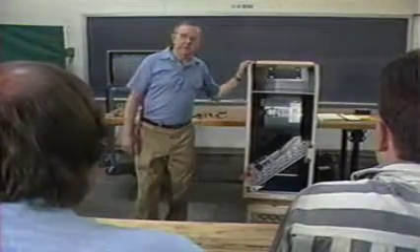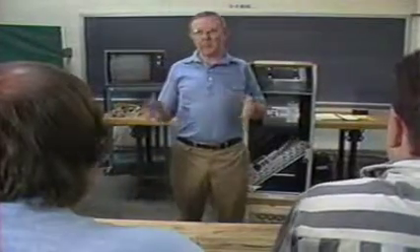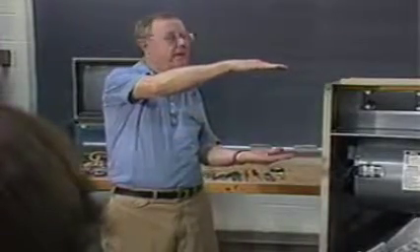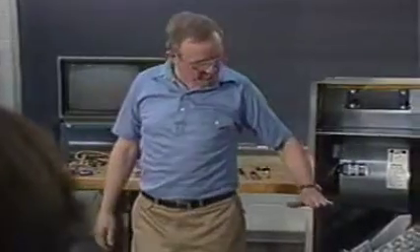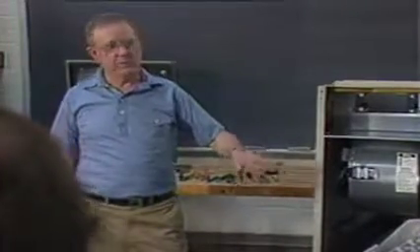Let's discuss the service call we just saw on the video. The air was too cold coming out of the registers — our problem in this whole video is restricted air flow. To test for how much cold air is coming out of the registers, we can do this without an instrument using a practical test: if air is only coming out about a foot high, you don't have enough air flow. If you can stand over a floor register and feel the cold air up about waist high or a little above, you probably have enough air coming out.